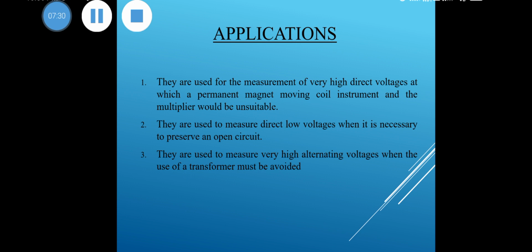There are some applications of the electrostatic voltmeter. They are used for measurement of high voltages at which a permanent magnet moving coil instrument and multiplier would be unsuitable. They are used to measure direct low voltages when it is necessary to preserve an open circuit. They are used to measure very high alternating voltages when the use of a transformer must be avoided. That is, electrostatic voltmeters are preferred for measuring high voltage AC and high voltage DC.